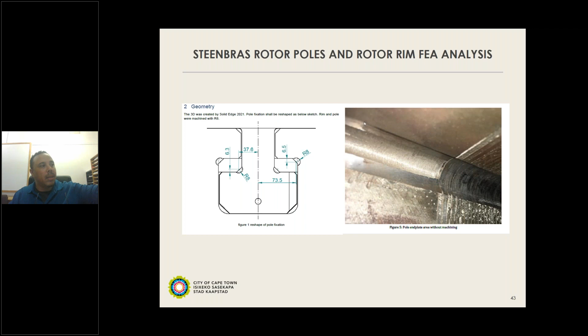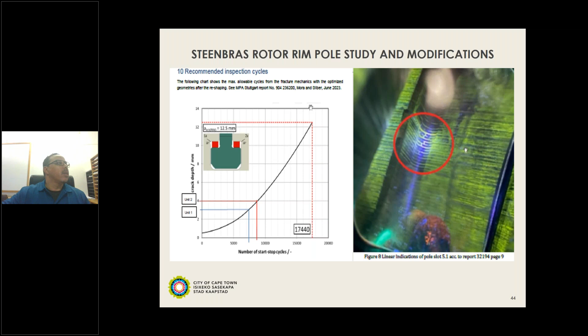The graph on the left shows that if you have a crack of a certain depth in millimeters identified on your machine, you're safely allowed to run for a certain number of cycles. By machining and redoing the rotor poles, we've gained the capability to run all 4 of our units, after these 2 outages, for quite a few more thousand cycles. Depending on how often we run, that equates to anywhere from 4 to 8 additional years on each unit, which will hopefully get us to refurbishment, which is the next thing I'll touch on.